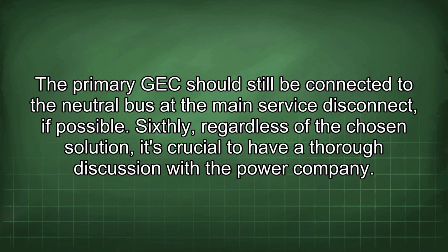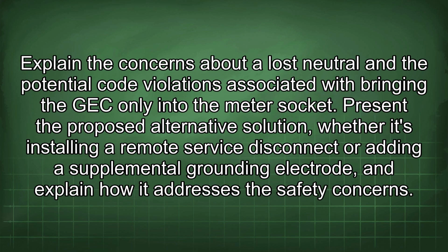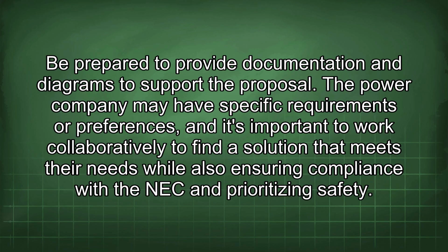Sixthly, regardless of the chosen solution, it's crucial to have a thorough discussion with the power company. Explain the concerns about a lost neutral and the potential code violations associated with bringing the GEC only into the meter socket. Present the proposed alternative solution, whether it's installing a remote service disconnect or adding a supplemental grounding electrode, and explain how it addresses the safety concerns. Be prepared to provide documentation and diagrams to support the proposal. The power company may have specific requirements or preferences, and it's important to work collaboratively to find a solution that meets their needs while also ensuring compliance with the NEC and prioritizing safety.